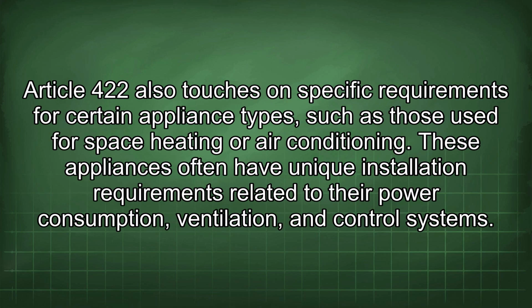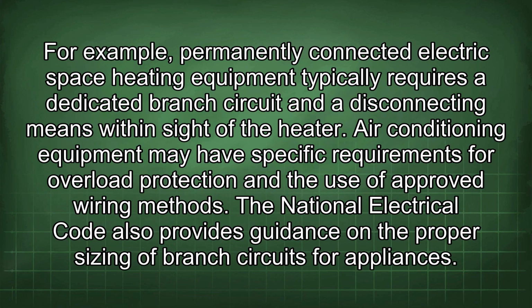Article 422 also touches on specific requirements for certain appliance types, such as those used for space heating or air conditioning. These appliances often have unique installation requirements related to their power consumption, ventilation, and control systems. For example, permanently connected electric space heating equipment typically requires a dedicated branch circuit and a disconnecting means within sight of the heater. Air conditioning equipment may have specific requirements for overload protection and the use of approved wiring methods.